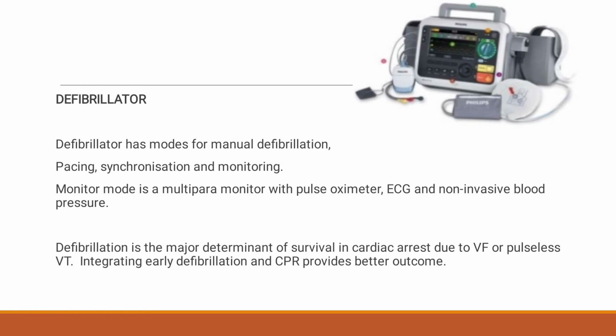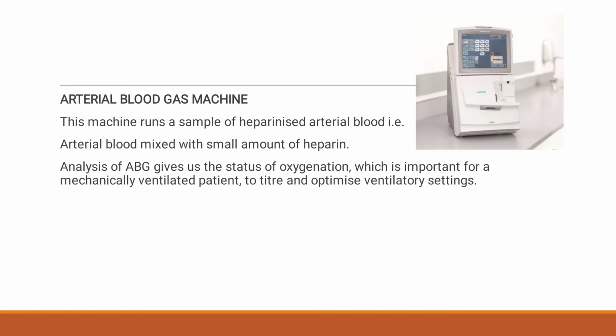Defibrillator. A defibrillator has modes for manual defibrillation, pacing, synchronization, and monitoring. The monitor mode is a multipara monitor with pulse oximeter, electrocardiogram, and non-invasive blood pressure monitoring. Defibrillation is the major determinant of survival in cardiac arrest due to ventricular fibrillation or pulseless ventricular tachycardia. Integrating early defibrillation and CPR provides better outcome.